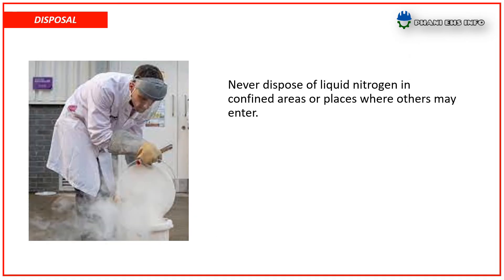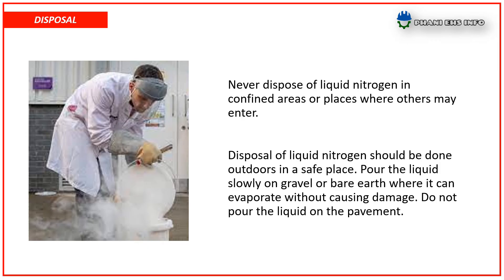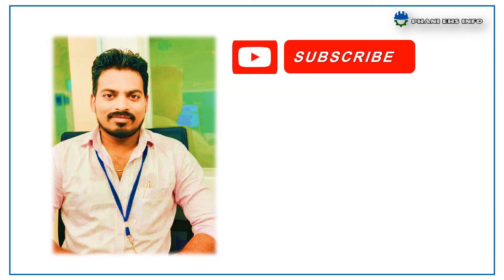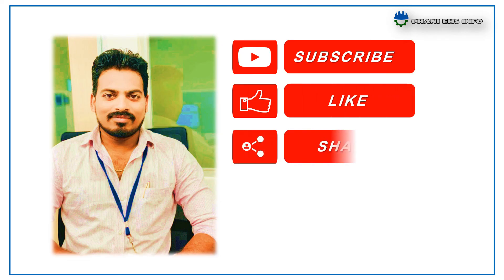How to dispose — never dispose of liquid nitrogen in confined areas or places where others may enter. Disposal should be done outdoors in a safe place. Pour the liquid slowly onto gravel where it can evaporate without causing damage. Do not pour the liquid on pavement. This concludes the topic of liquid nitrogen safety — hope you understand.